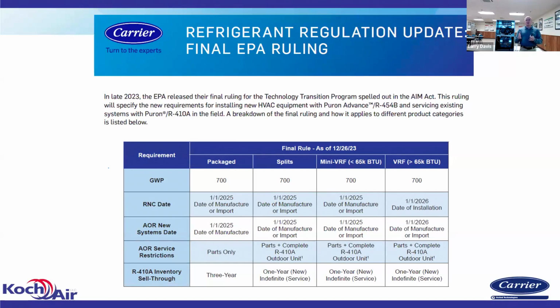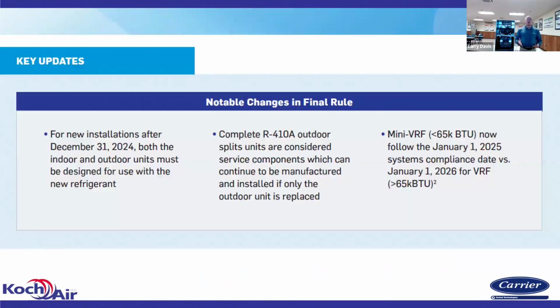So you see some dates there. We see 4 different categories: package units, split systems, mini VRF or ductless products, and then the larger VRF products. And there's some different dates there. A couple of those I don't think this slide's quite correct on, but the bottom line here is starting the end of this year, January 1st, 2025, if it's a new system going in, that new system has to have the low GWP refrigerant in it. In other words, if you have a system that you're installing after January 1st, it cannot be a 410A system. It has to be the 454B.